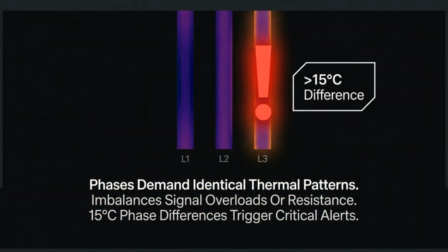All 3 phases must exhibit identical thermal patterns. Imbalances signal overloads or resistance. A 15 degrees Celsius phase difference should trigger a critical alert.